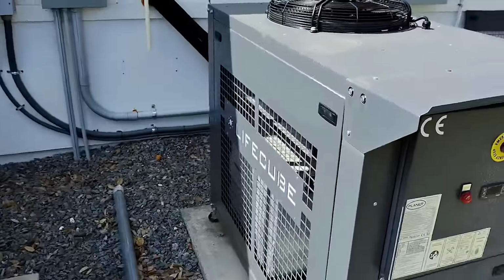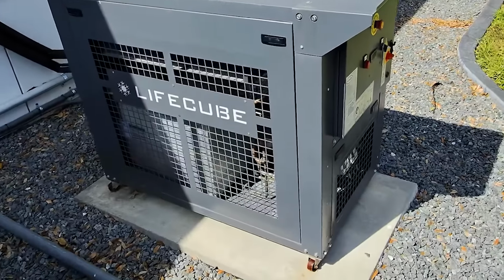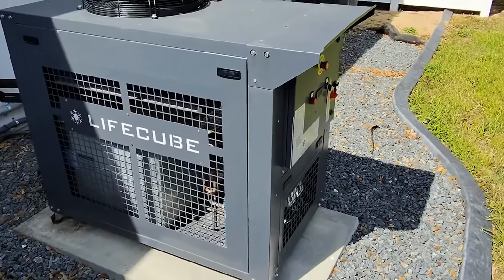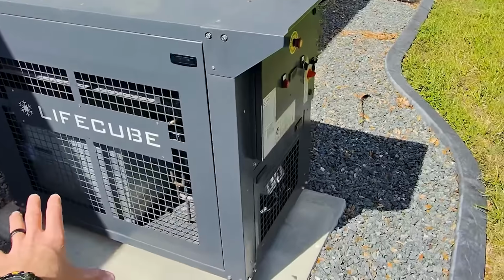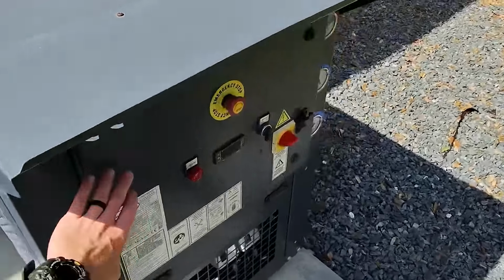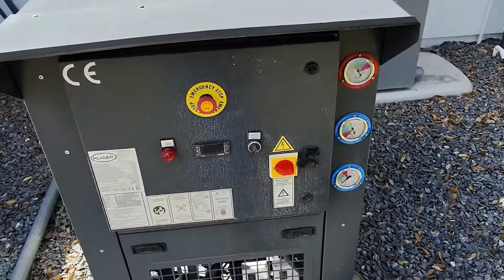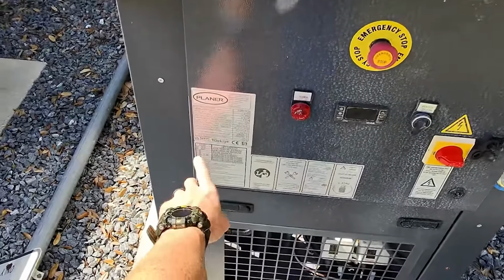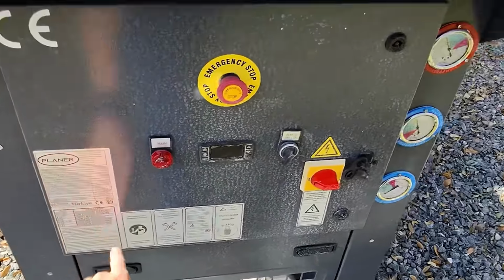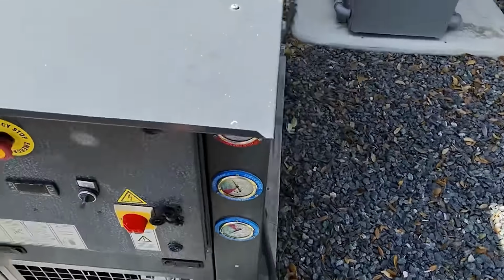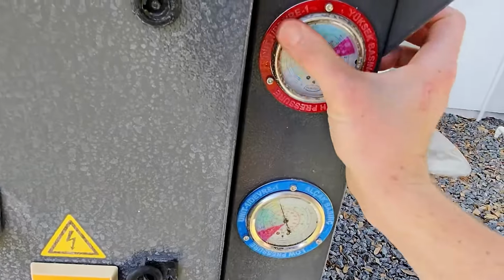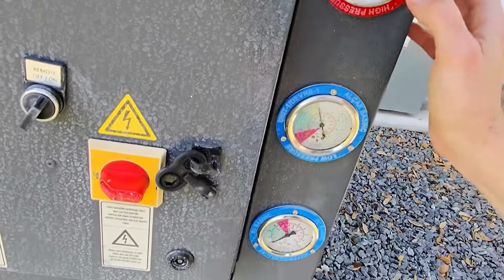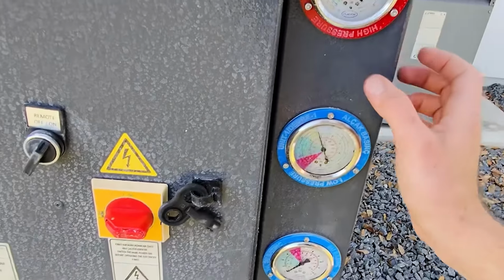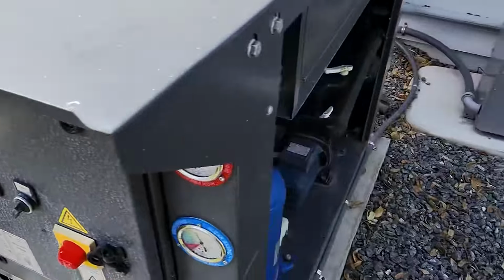So what we've got here is a LifeCube brand chiller. So this is a remote condenser. We've got a control interface here, and it does have an alarm. Actually, it's an A16, which is water pump overload warning. That isn't the main problem. It's a nice little touch here. We've actually got some pressure gauges, both low pressure, high pressure, and water pressure.